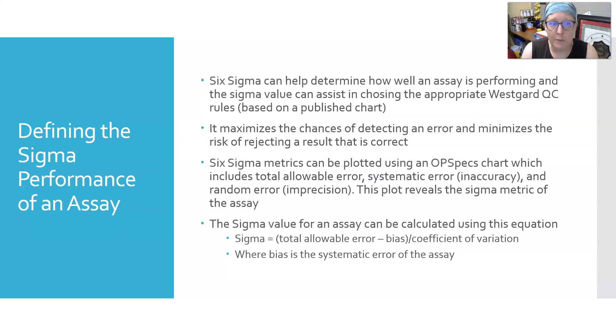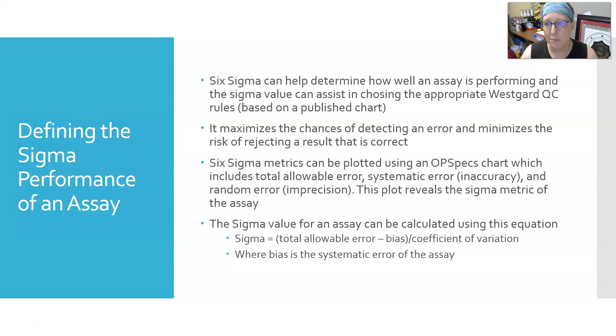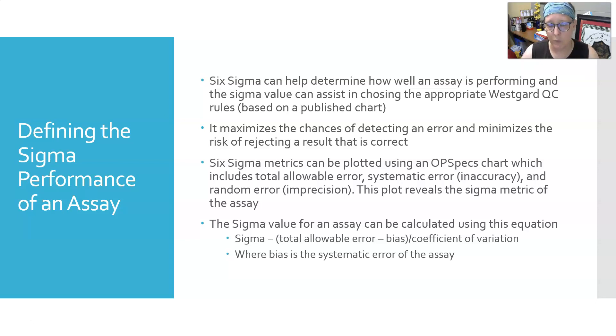Six sigma can help determine how well an assay is performing. The sigma value can assist in choosing the appropriate Westgard QC rules to help flag when problems are developing — based on published charts you can look up. This maximizes the chances of detecting an error and minimizes the risk of rejecting a correct result. Six sigma metrics can be plotted using an OP specs chart, which includes total allowable error, systematic error (inaccuracy), and random error (imprecision). This plot reveals the sigma metric of the assay, ranging from one to six sigma, and determines which Westgard QC rules to use. The sigma value of an assay is calculated as: sigma = (total allowable error − bias) / coefficient of variation, where bias is the systematic error of the assay.